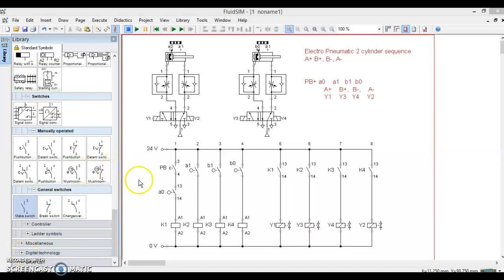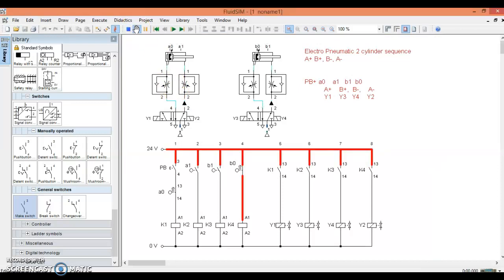In the previous video we proved that we had a problem with trapped signals. With this sequence, if I put the system in run and try to make it operate, you can see here when I do that Y1 attempts to come on but there's a problem because Y2 is already active.